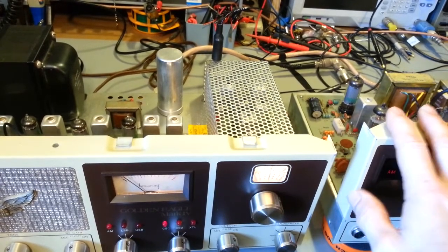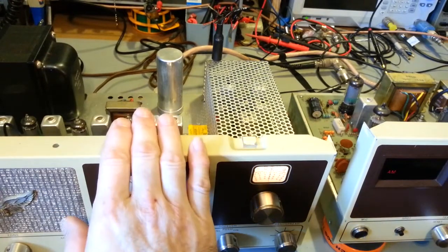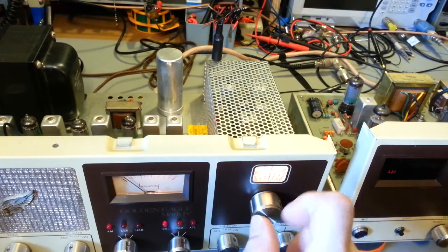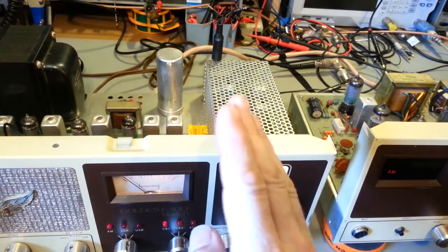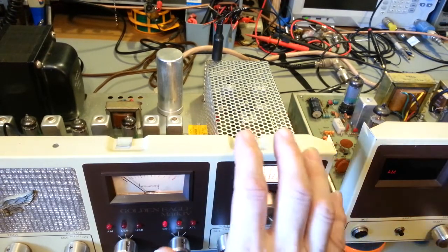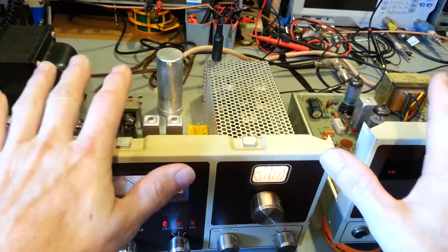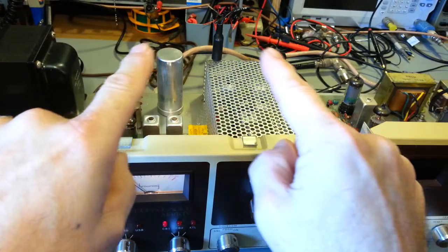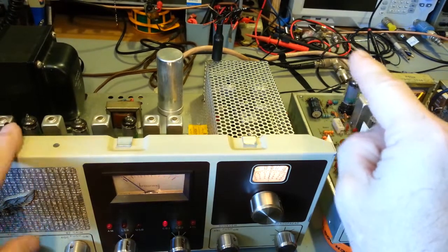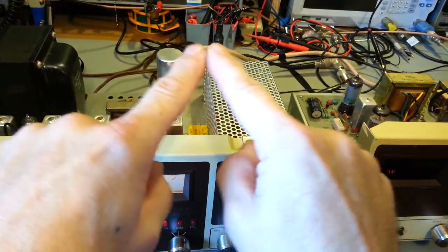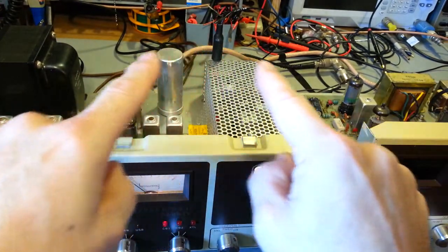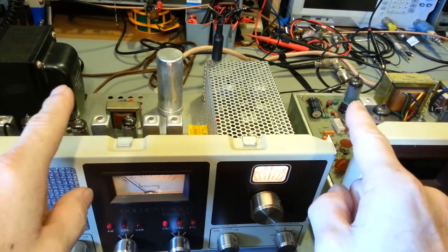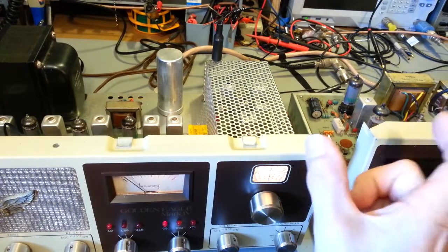The reason for that is if you do this alignment, let's say you were to set this transmitter on channel 1, and you do your alignment on channel 1, there's a high probability that then your receiver, by the time you get to channel 40, receiver sensitivity is going to start to drop off. So we want to peak this circuit in the center of the frequency range that the radio works on, so it drops off evenly, maybe towards the outside edge. We don't want to peak it at one end, and then by the time it gets down here to the other channel, it's dropped a noticeable amount. If you peak it at the center frequency, the amount of drop-off you'll have over just 20 channels in either direction really isn't going to be noticeable. So that's why you always want to pick the center frequency.